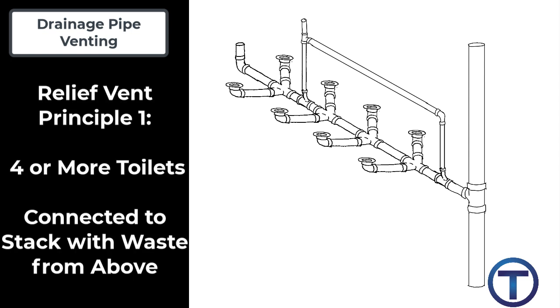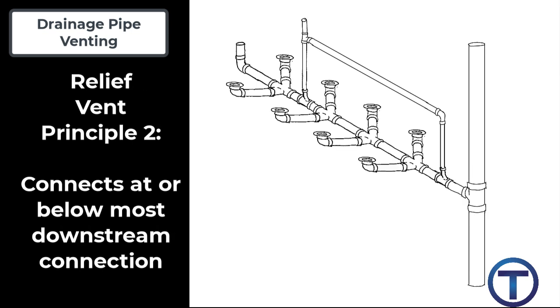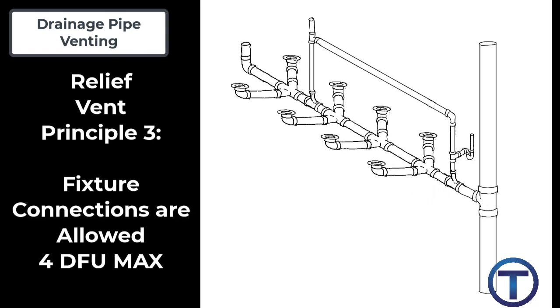Relief vent principle one: the relief vent is required when a horizontal branch with four or more toilets connects to a stack receiving waste from an upper floor level. Relief vent principle two: the relief vent is to be installed at or below the most downstream fixture in the circuit. That would mean it connects just before that horizontal branch connects to the stack.